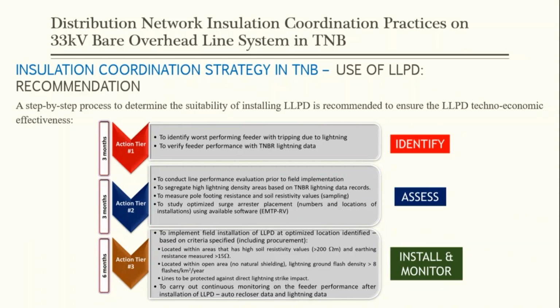And the next 6 months, or action tier 3, is to install and monitor. That is, to implement the field installation of the LLPD at optimized locations identified based on the criteria specified before, and to carry out continuous monitoring of the feeder performance after installation of the LLPD with the use of auto recloser data and lightning data.